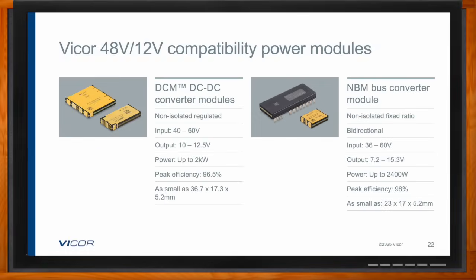You can see in this slide the DCM is shown. In this case, there's a 48-to-12 DCM shown in a non-isolated regulated package. The input is 40 to 60, which is very common in high performance computing. The Open Compute spec I mentioned earlier specifies 40 to 60 volts in, and it regulates at 12 volts, but can be easily trimmed down to 10 or up to 12.5. There are two package sizes, with the highest power up to 2 kilowatts, and efficiency is very impressive at 96.5% for a regulated converter. The small package size, 36 by 17 with a 5.2 millimeter height, is also impressive.